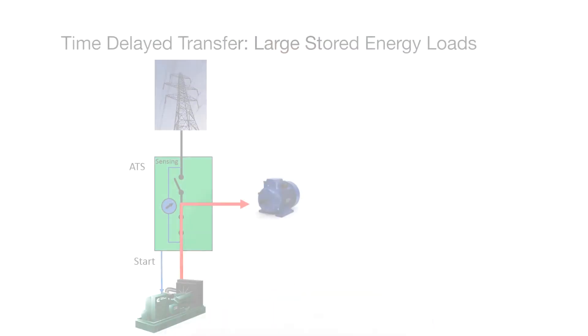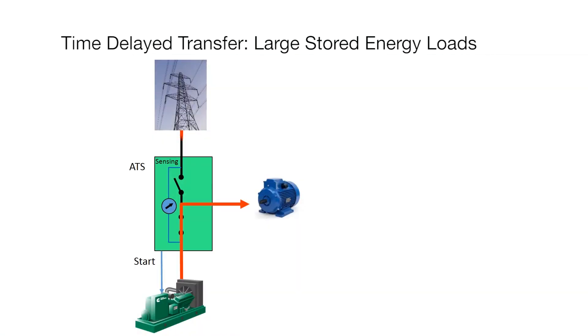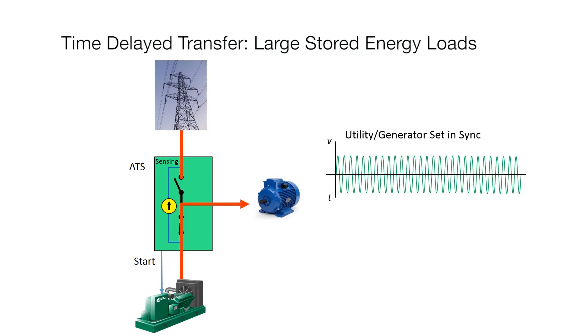If a large motor load is powered by the generator and the utility source becomes available, before transferring back to the utility source, the ATS mechanism stops in the center-off position for a predefined amount of time to allow the residual voltage to decay to a safe level.